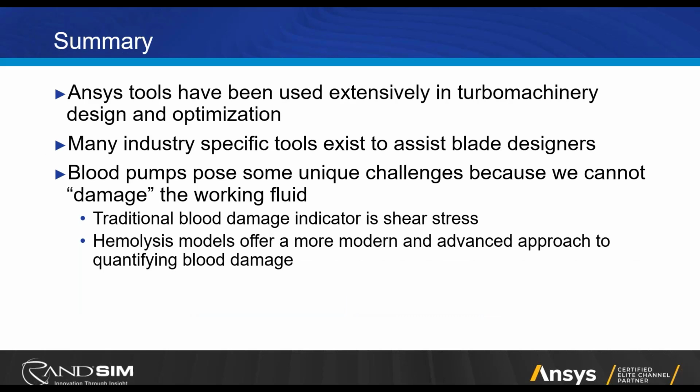Okay. In summary, it was a quick look at the different tools that we have that are tailor-made for the turbomachinery industry. These pumps pose unique challenges that we don't really consider in traditional turbo design. Who cares about damaging the working fluid in other industries? That's unique to blood pumps.